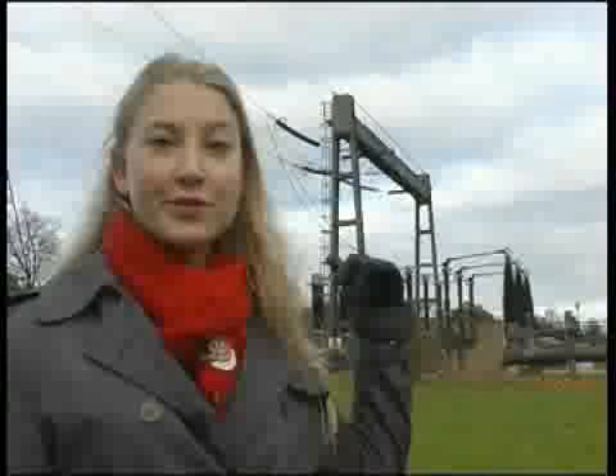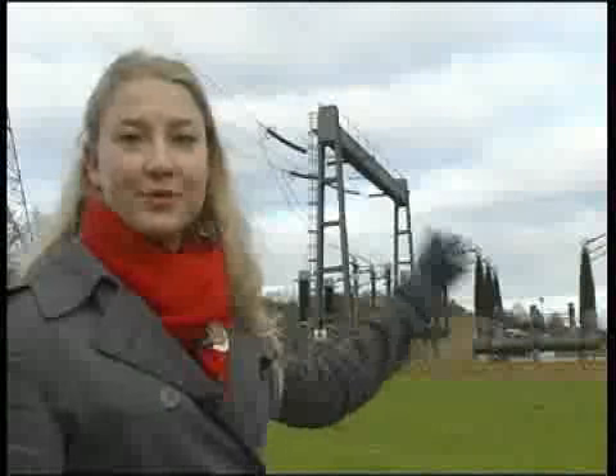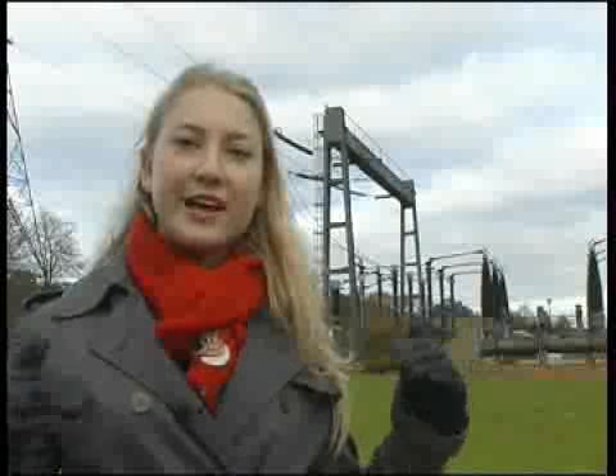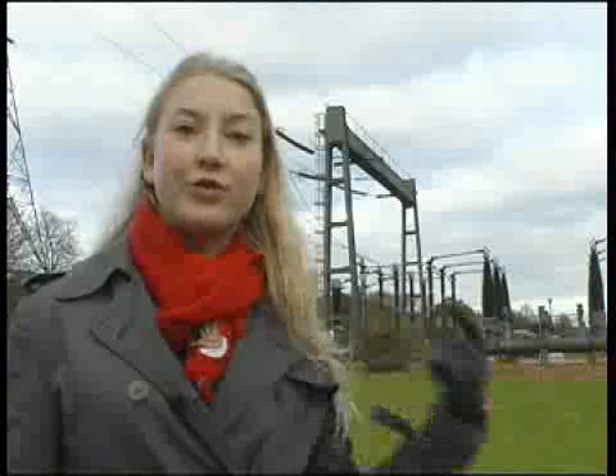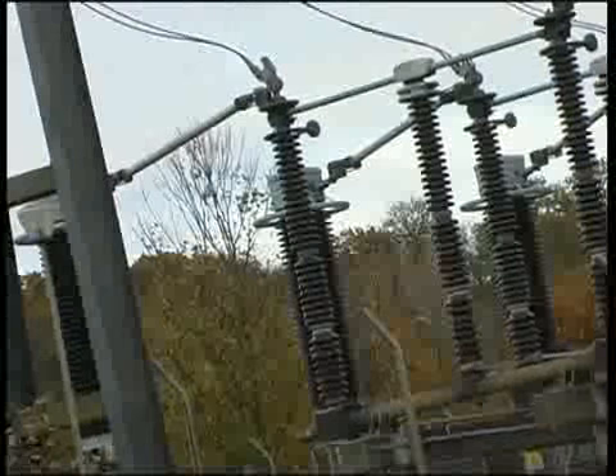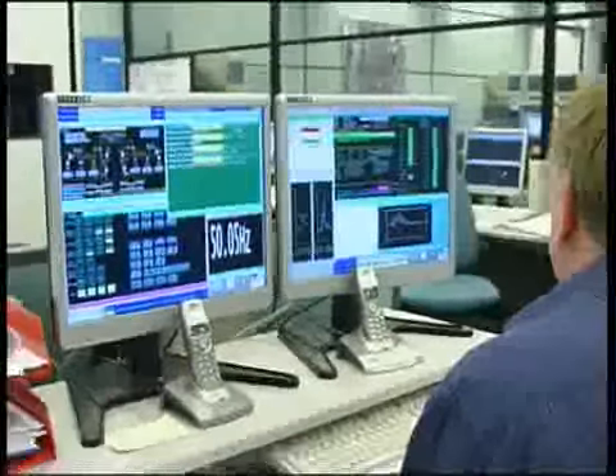Here we are right by the national grid, so we can draw energy straight down to power JET. In order to even out our demand on the grid, we draw the energy down slowly, and we store it on two large flywheels, 780 tons each, spinning at up to 225 revolutions per minute. During the pulse, the energy needed to create the magnetic fields to control the plasma comes from the flywheels, and they slow down. More energy comes from the grid to heat the plasma to high temperatures. As the flywheels approach the required speed, we begin countdown.